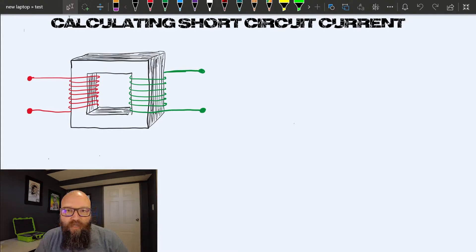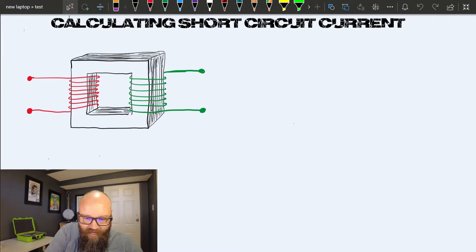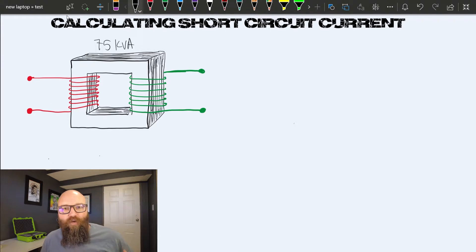I've got a basic transformer drawn here. This is just a single phase. We've got our primary winding in red and our secondary winding in green. I'm going to give you the basic numbers needed to perform a short circuit calculation. First off, this is a 75 kVA transformer. What we know about transformer theory is KVA in equals KVA out.